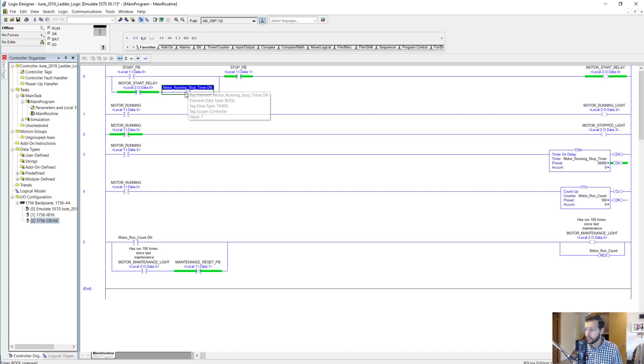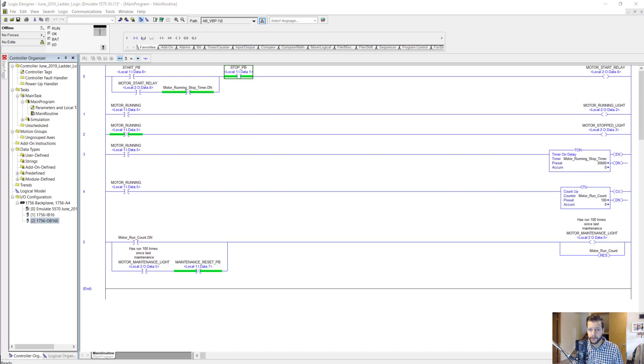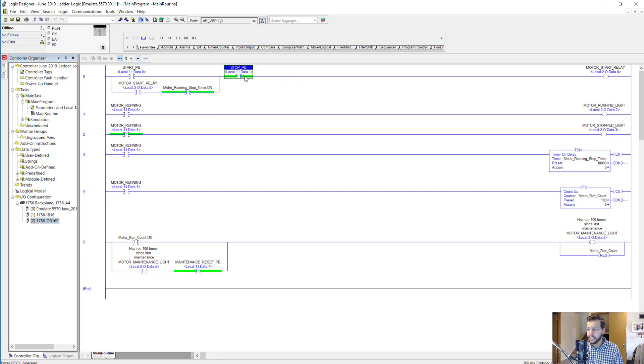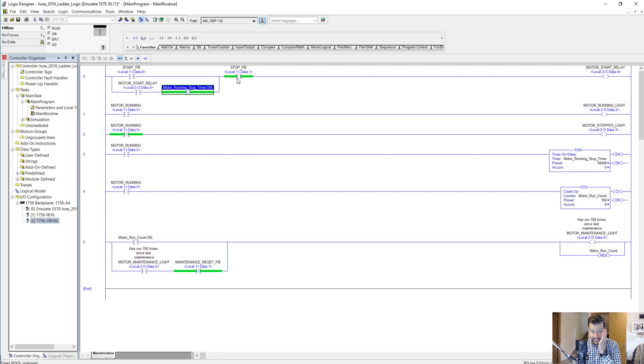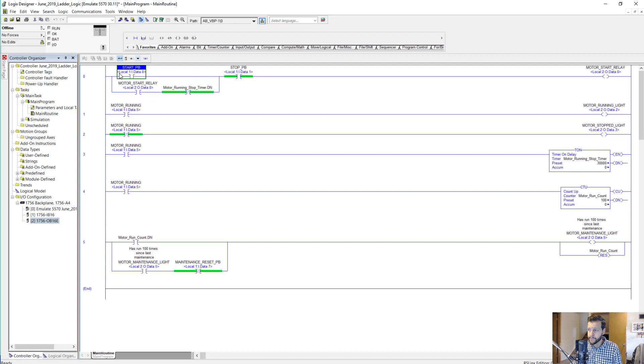Now one last thing about this rung I want to talk about is the stop push button. Here's two questions to consider. First, why is the stop push button up here rather than here like the motor running stop timer dot done? And second, why is it an XIC instead of an XIO like this one? For the first question, having the stop push button here allows it to not only interrupt the seal-in circuit path, but it also prevents us from starting it in the first place if the stop push button is pressed.